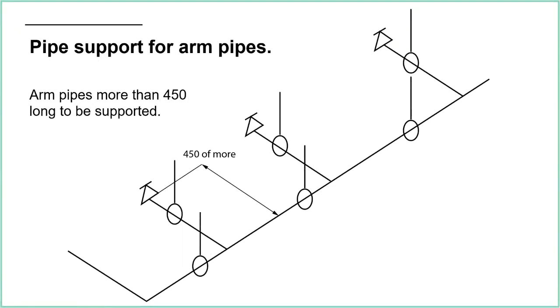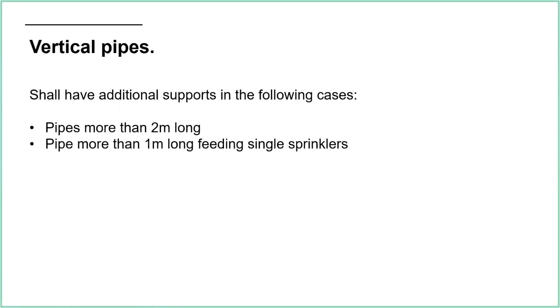Arm pipes, similar thing. Arm pipes more than 450 millimeters long need to be supported. If they're shorter, then they don't. Some rules on vertical pipes. So any vertical pipe that's more than 2 meters long, or more than 1 meter long feeding single sprinklers, would need to have additional supports in place.